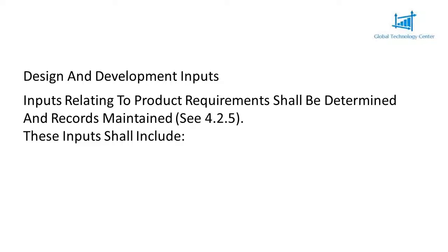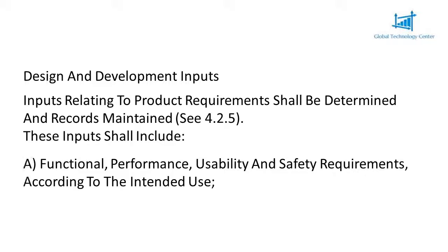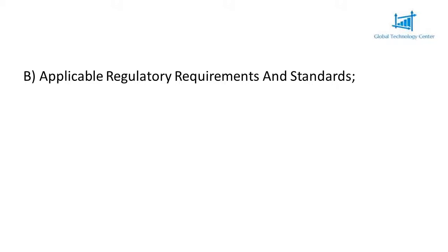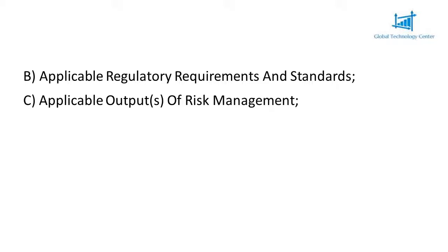Design inputs shall include: A. Functional, performance, usability and safety requirements, according to the intended use. B. Applicable regulatory requirements and standards. C. Applicable outputs of risk management.